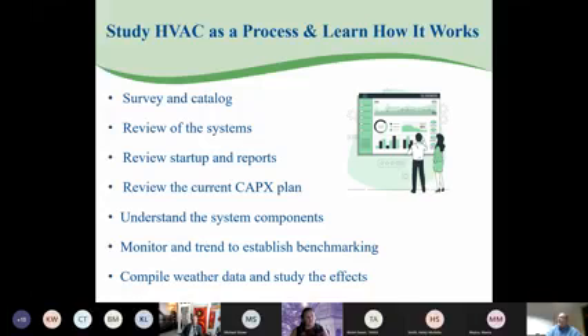Review the current CapEx plan if you have one. CapEx being a capital expenditure plan. ASHRAE has published a chart that lists estimated life expectancies for various HVAC equipment. So where are you at in the life cycle of your equipment? Attached to this presentation should be an ASHRAE sheet giving the life expectancy of most equipment. Rooftop ACs generally last for 15 years. Heat pumps, 15 years. Chillers and cooling towers have a 20-year life. Electronic controls have a 15-year life.